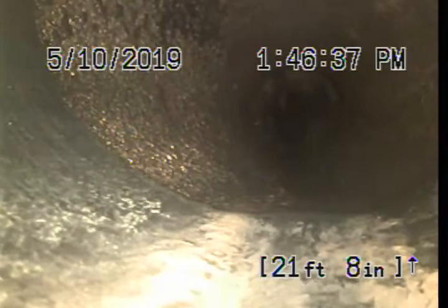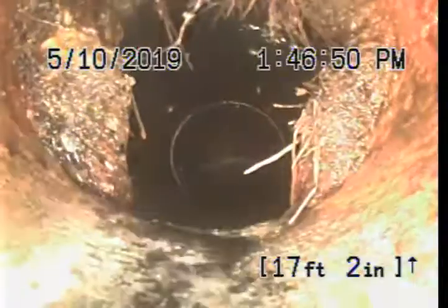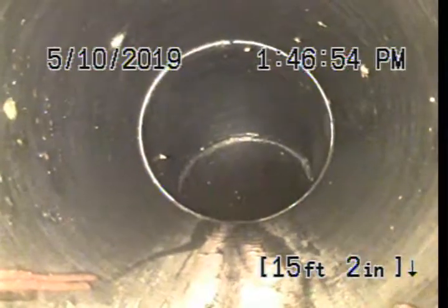Okay, so here at 21 feet, we're converting from that concrete pipe into an ABS plastic. ABS plastics are an excellent material for main sewer lines. They have a long service life expectancy. They're also intended to be impervious to root intrusions. And lastly, they have a smooth inner surface, which makes them very efficient at washing out debris.